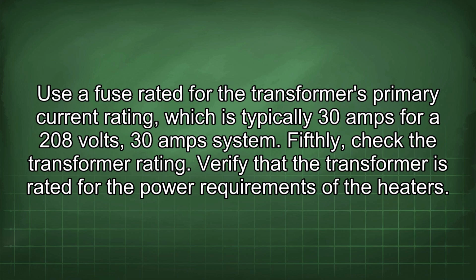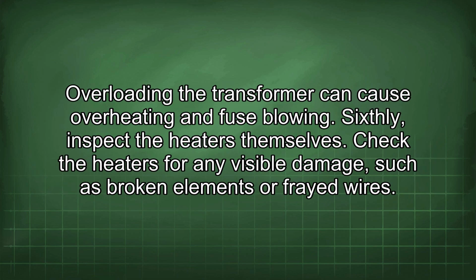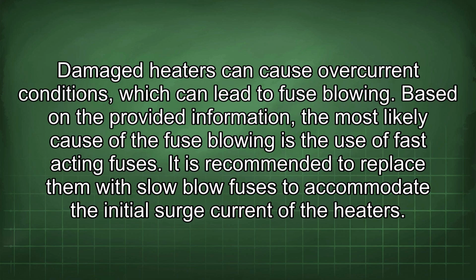Verify that the transformer is rated for the power requirements of the heaters. Overloading the transformer can cause overheating and fuse blowing. Sixthly, inspect the heaters themselves. Check the heaters for any visible damage, such as broken elements or frayed wires. Damaged heaters can cause overcurrent conditions which can lead to fuse blowing.